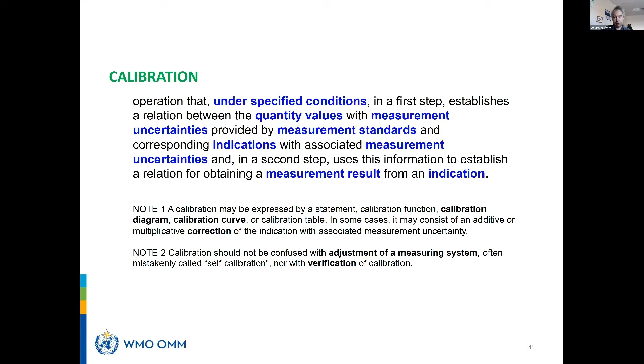This is only one part of the overall measurement uncertainty, because the calibration is done in the lab under controlled conditions. This is what the VIM says: under specific conditions. Then I use the instrument in the field, and those conditions are different. The calibration procedure should be such that the instrument is calibrated, as far as possible, in the same conditions you will use it later on.